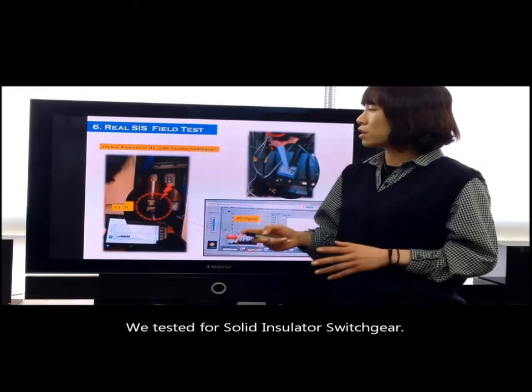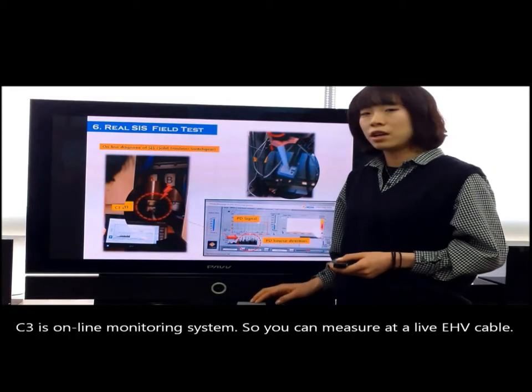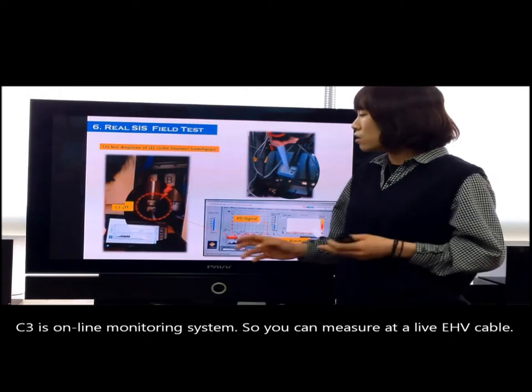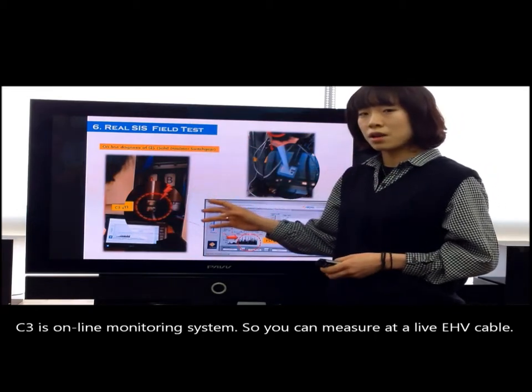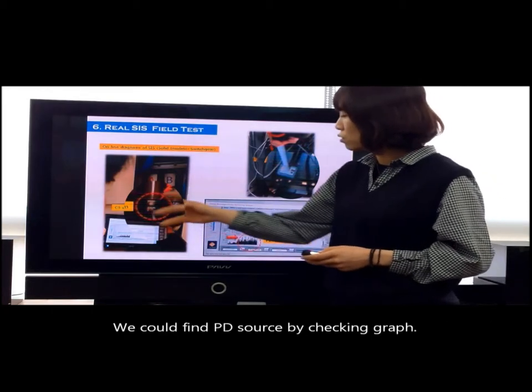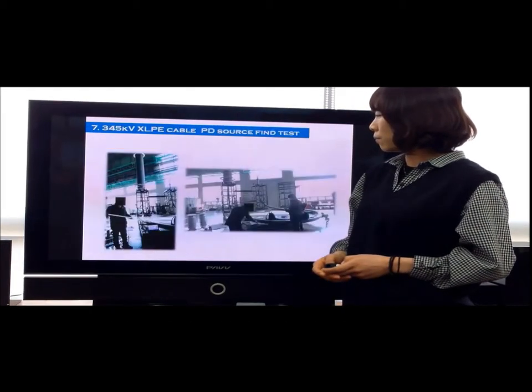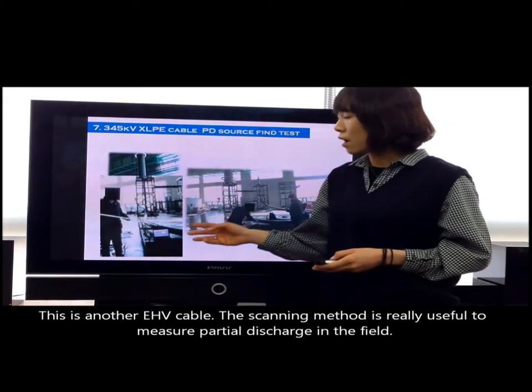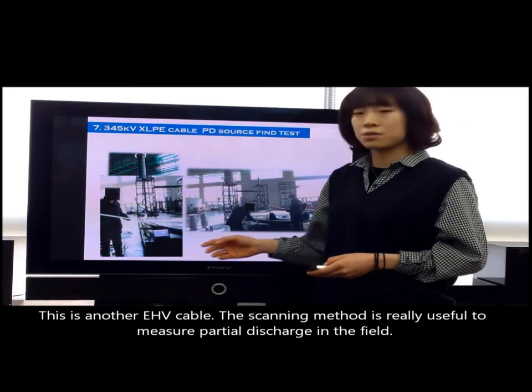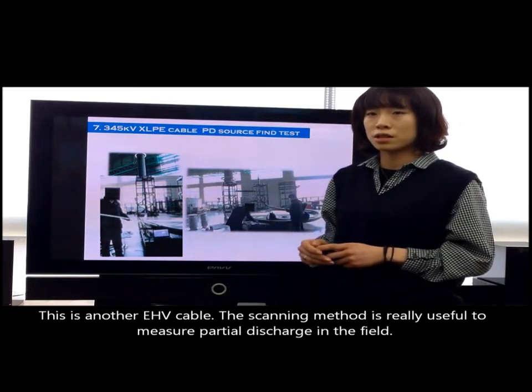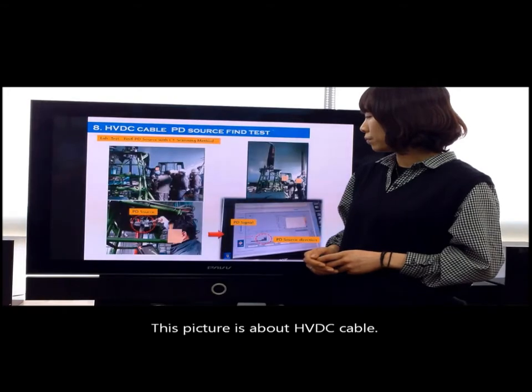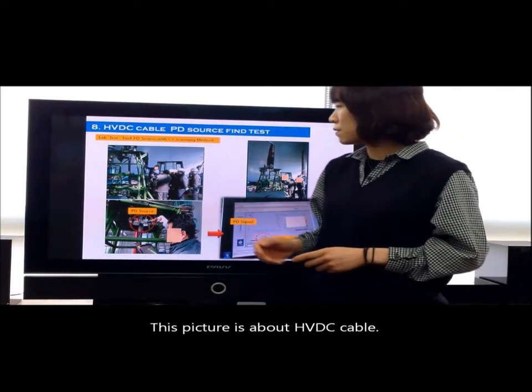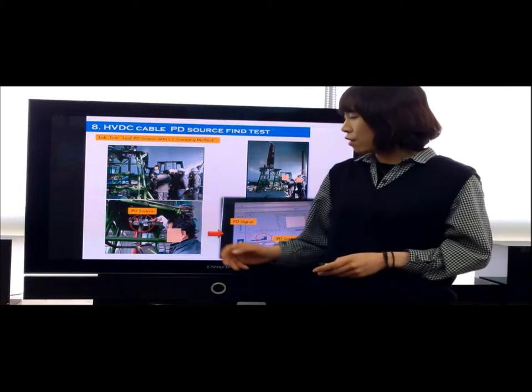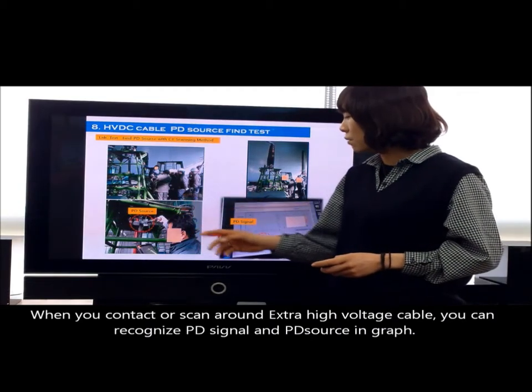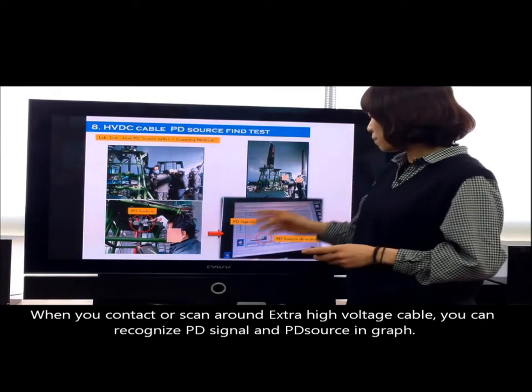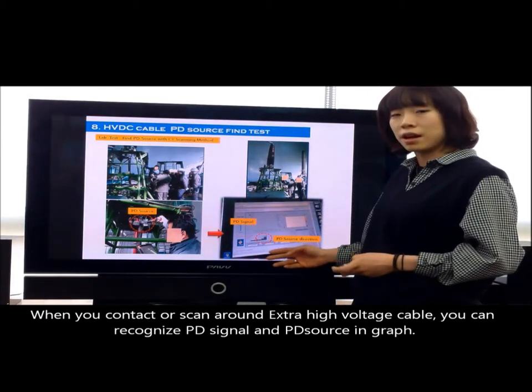We tested a solid insulator switchgear. C3 is an online monitoring system, so you can measure at a live extra high voltage cable. We could find the PD source by checking the graph. This is another extra high voltage cable. The scanning method is really useful to measure partial discharge in the field. This picture is about an HVDC cable. When we contact or scan around the extra high voltage cable, you can recognize the partial discharge signal and PD source in the graph.